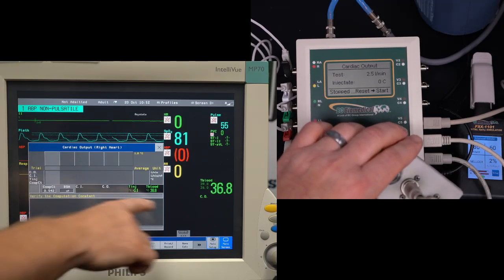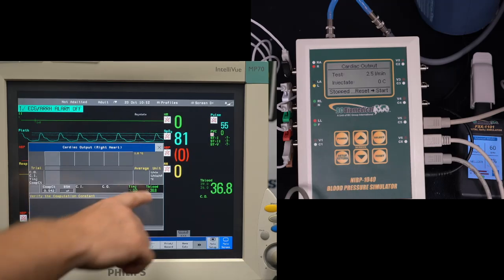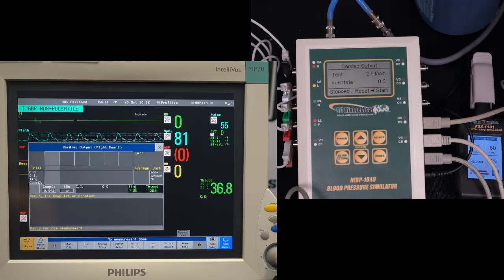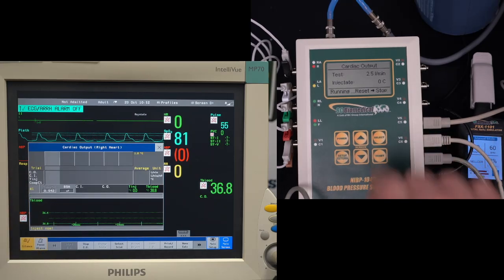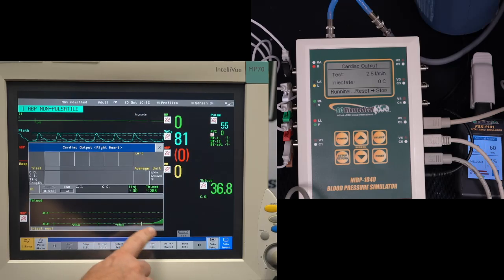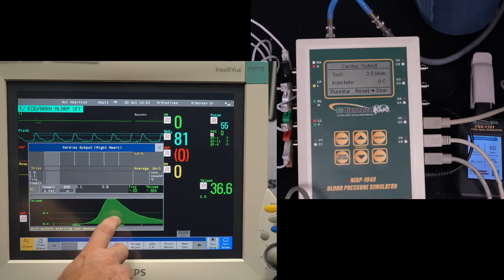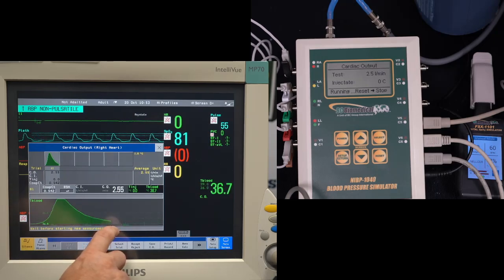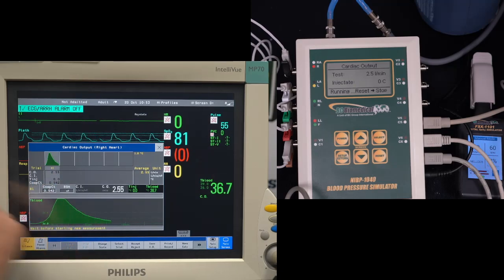And it's also going to show the blood temperature over here. So we're injecting ice water into the heart, and we're measuring the output. I'll press start here on the cardiac output and inject now. So I'll go ahead and do the injection, and we'll see that we're simulating that injection into the heart, which should provide a flow measurement when it's complete. And there we go. So it measured 2.55, and I had 2.5 set on the NIBP.